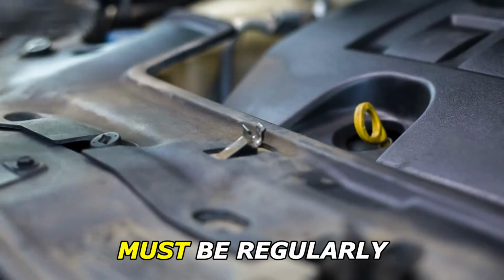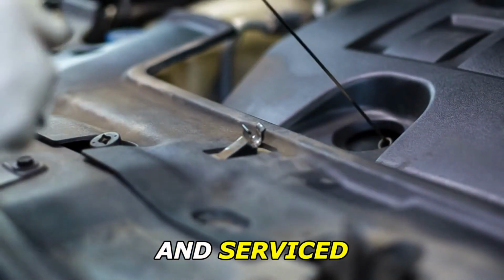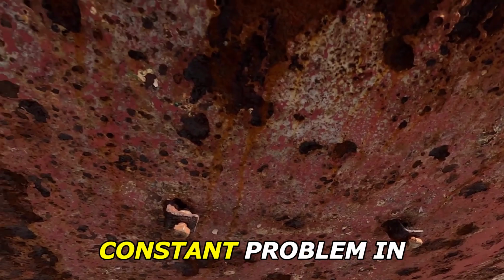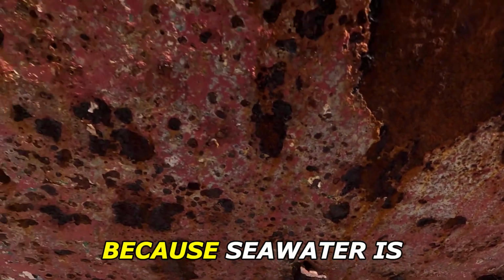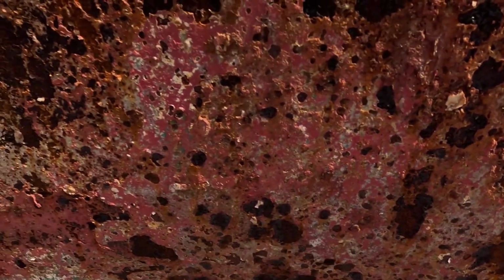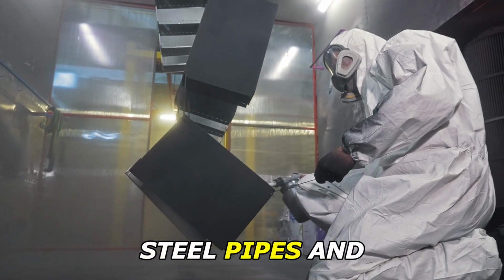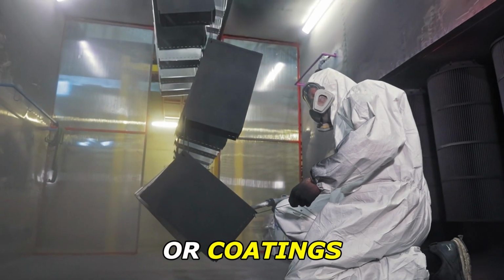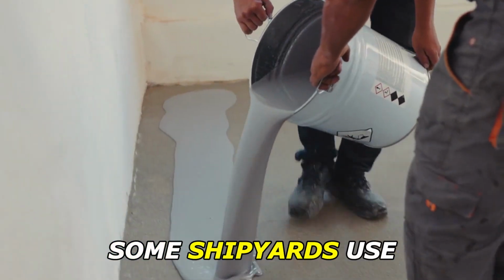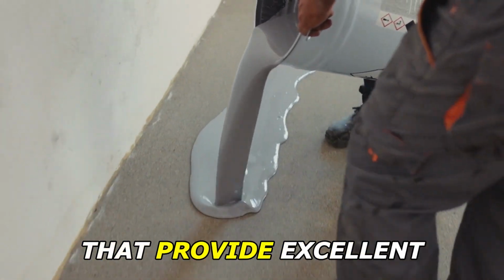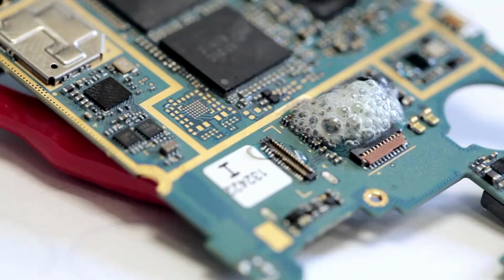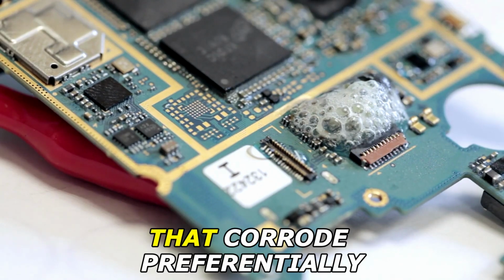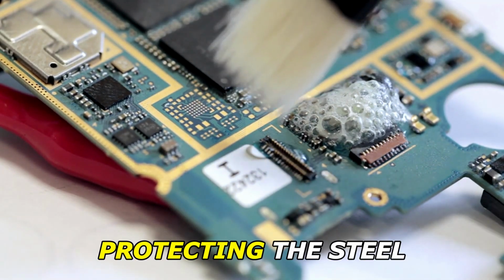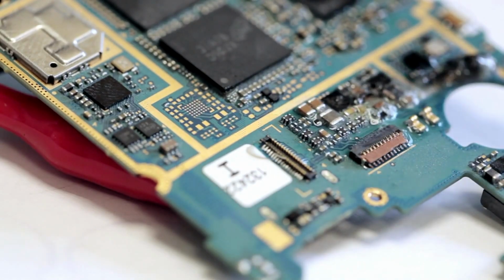The ballast pumps must be regularly inspected and serviced. Corrosion is a constant problem in the ballast system because seawater is extremely corrosive. Steel pipes and tanks must be protected by paint or coatings. Some shipyards use epoxy coatings that provide excellent protection. Others use sacrificial anodes that corrode preferentially to the steel, protecting the steel from corrosion.